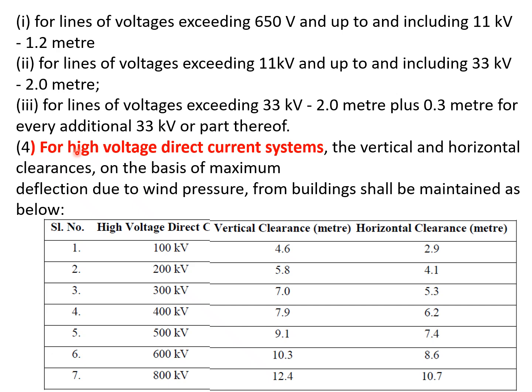Fourth, for high voltage direct current systems, the vertical and horizontal clearances from buildings, on the basis of maximum deflection due to wind pressure, shall be maintained as below: 100 kV, 4.6 meter vertical and 2.9 meter horizontal, and so on up to 800 kV, where the vertical clearance will be 12.4 meter, whereas the horizontal clearance will be 10.7 meter.